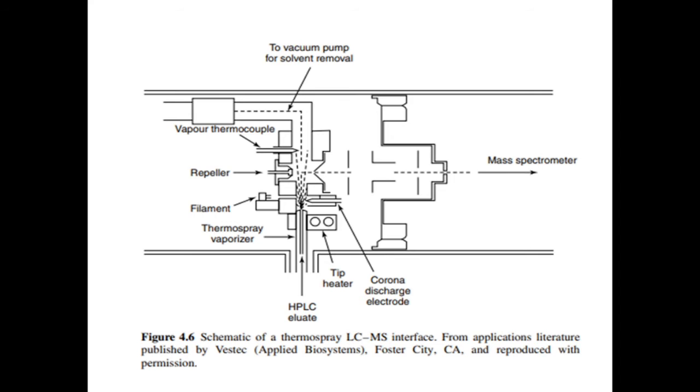This consists of a heated capillary through which the liquid chromatography eluate flows, with the temperature of this capillary being carefully controlled to bring about around 95% vaporization of the liquid. The vapor so produced acts as a nebulizing gas and aids the breakup of the liquid stream into droplets.